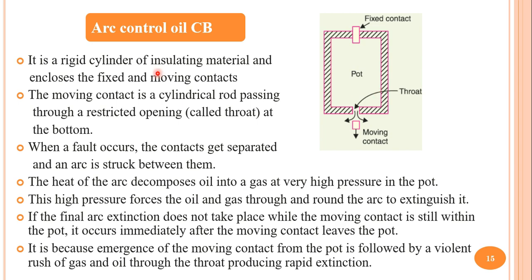In an arc control oil circuit breaker, a rigid cylinder of insulating material is used and fixed and moving contacts are placed in the pot. The moving contact is a cylindrical rod passing through a restricted opening at the bottom of the cylinder. When a fault occurs, contacts get separated and an arc is struck between them. The heat of the arc decomposes oil into hydrogen gas; since it is a closed pot completely filled with oil, high pressure is produced inside the pot. This high pressure forces oil and gas through and around the arc, with high turbulent motion of gas and oil helping to extinguish the arc.